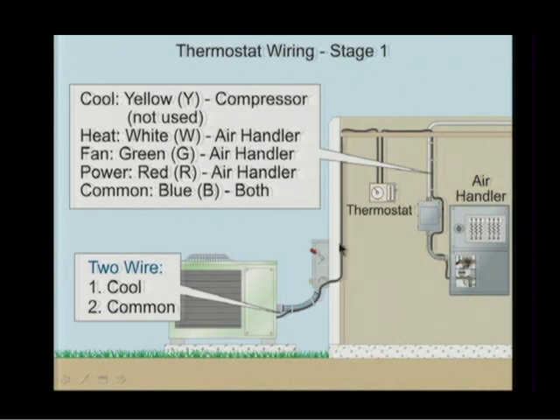If this was the wiring configuration, the blue wire comes over to the thermostat, and since that's common to the transformer, the blue wire will travel through this cable and go back over to the blue terminal that's going to go to the common of the transformer. If I can take 24 volts to the relay of the compressor, it closes those contacts, and the compressor kicks on. Let's talk about the fan. The fan has a common that also goes over to the transformer. And the fan is going to be controlled by the thermostat, and the fan is the green colored conductor.